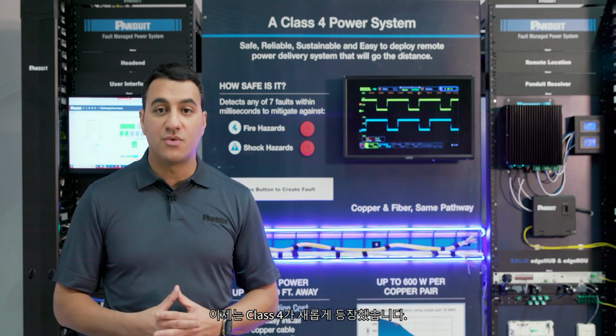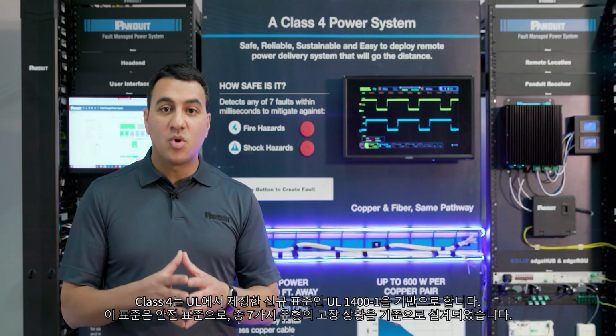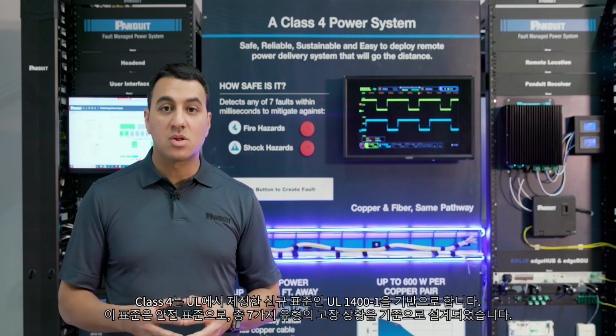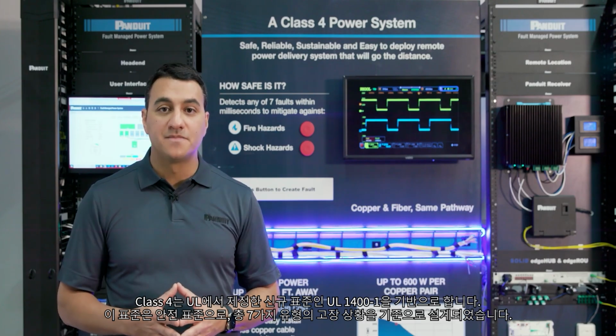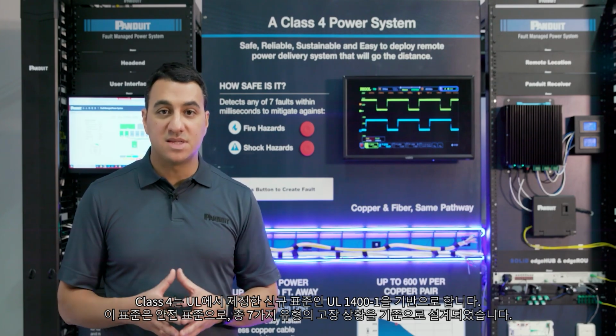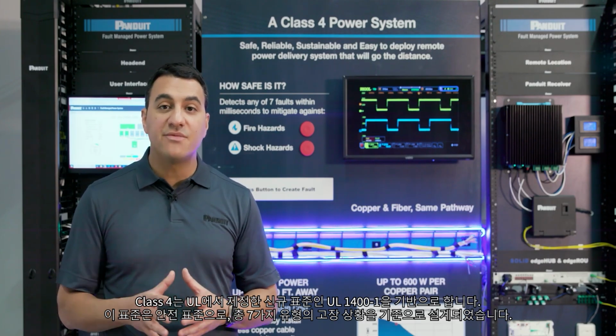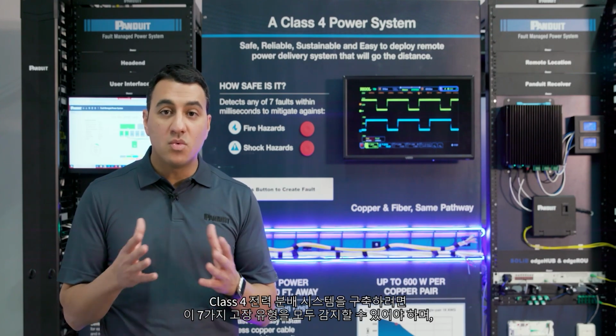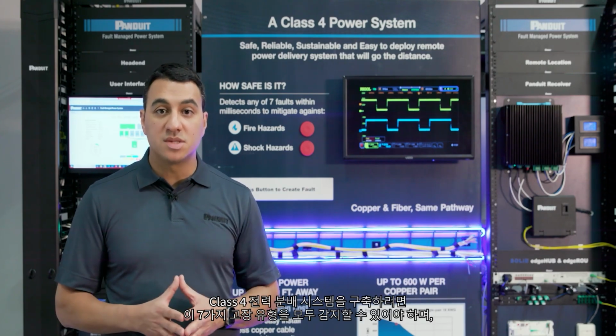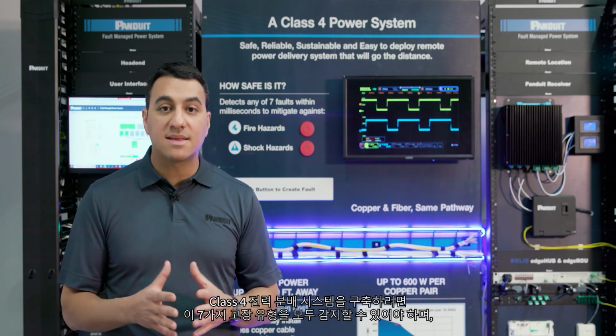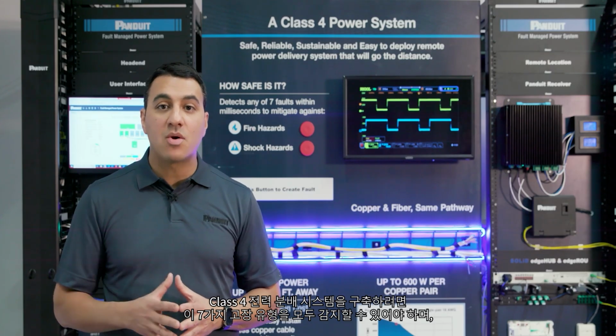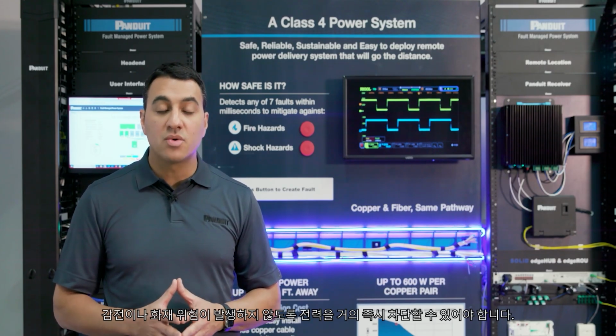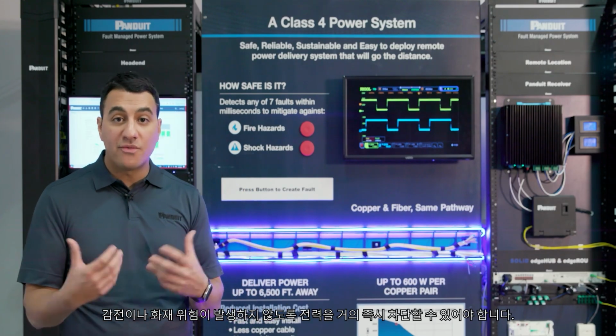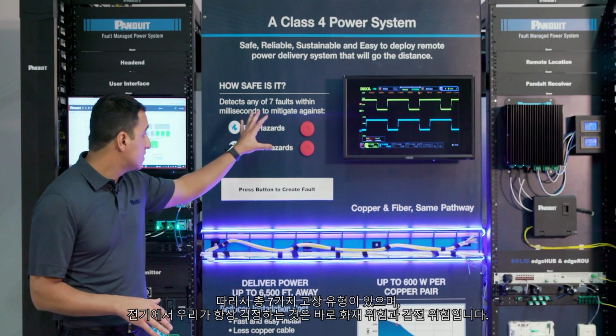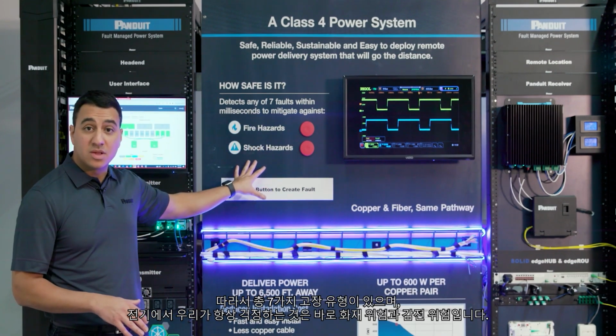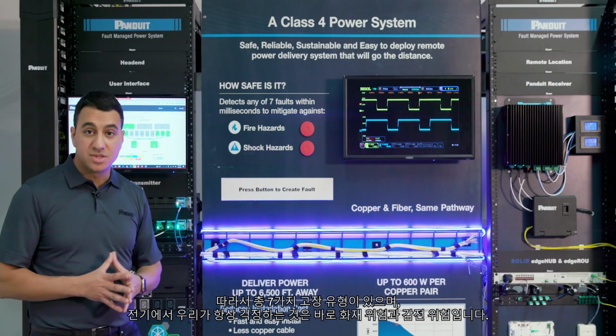But now there's Class 4. Class 4 is pointing to a new standard by UL called UL 1400-1. This standard is a safety standard. It's concerned with 7 different types of faults that if you were to develop a Class 4 power distribution system, you must be able to detect any of these 7 faults and turn power off almost instantly to make sure it doesn't cause any shock or fire hazard. So there are 7 faults, and this is what we're always concerned with: electricity, fire, and shock hazards.